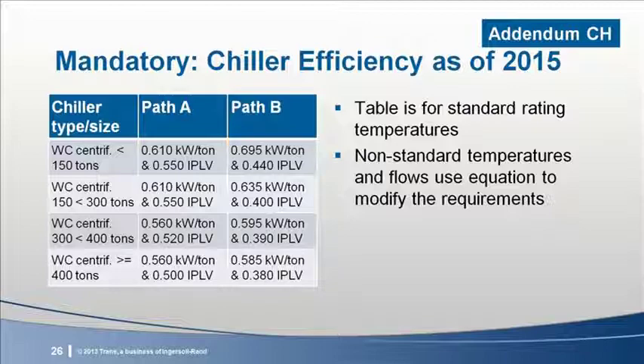The more significant movements, though, are in IPLV, especially for Path A. These requirements apply only to chillers optimized at standard rating conditions. For chillers optimized at non-standard rating conditions, there are equations to use with a spreadsheet that the 90.1 committee created to generate the requirements for these chillers. The scope limits are the same as for 2010.